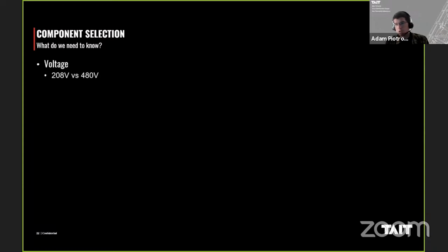Voltage is certainly one of those things. In North America, we have two main voltage classes: 200 volts, which we see as 208, and we have 400 volt class, which appears as 480 volts. This is going to determine what components you end up picking. Not everything can run from 200 volts to 500 volts, so you may have to change part numbers, you may have to change fuses.